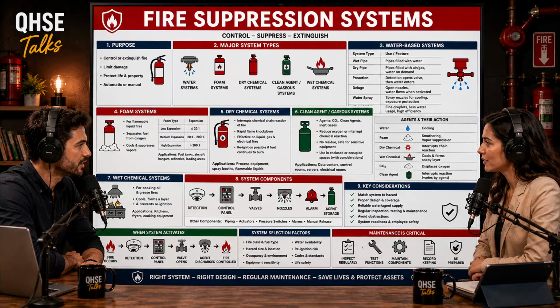Why is that a critical failure point? Because that layer of dust or paint acts as thermal insulation. It physically insulates the heat-sensitive glass bulb from the ambient air. So it drastically increases the thermal lag we discussed earlier. Yes. If a fire breaks out, the air temperature might reach 160 degrees, which should easily activate a 135-degree head. But the thermal element is insulated by paint. It doesn't feel the heat, so it doesn't melt. And the fire just keeps growing.